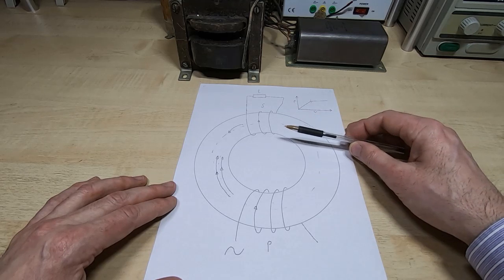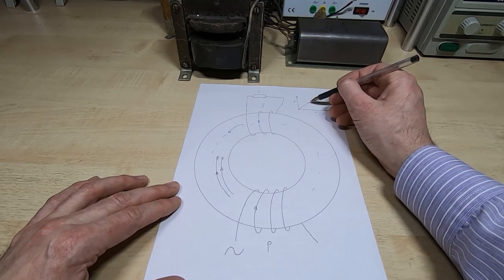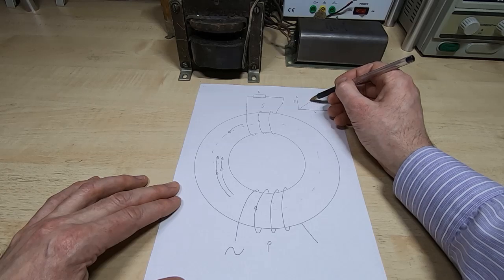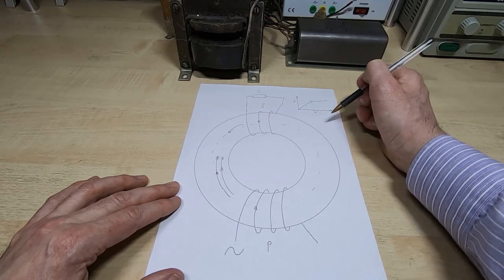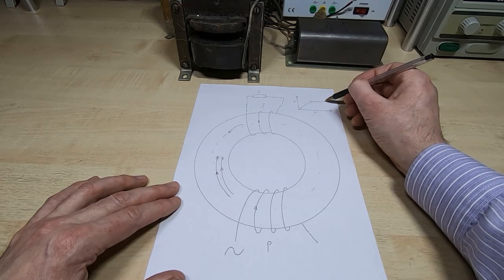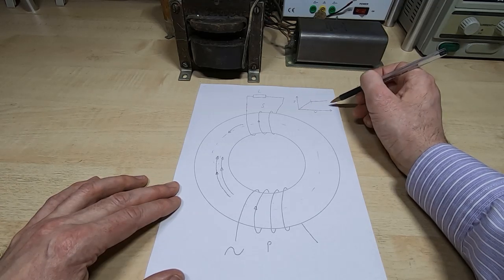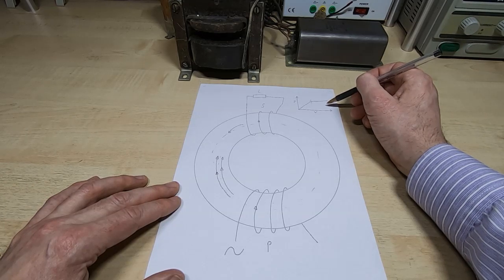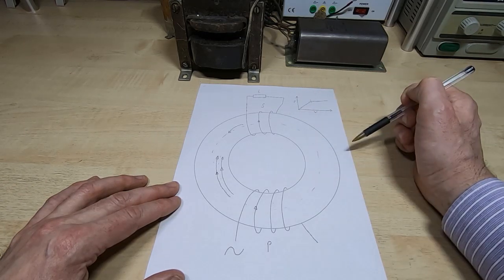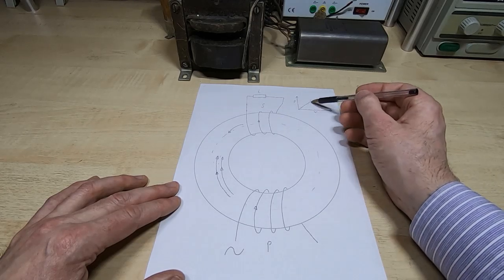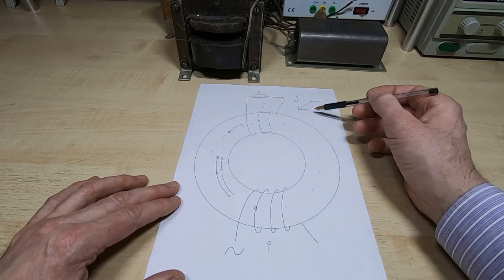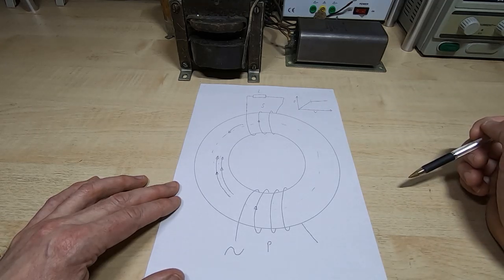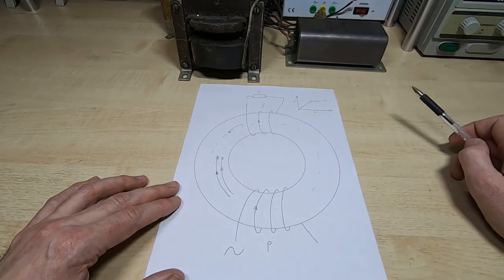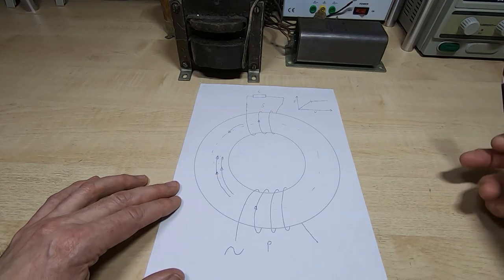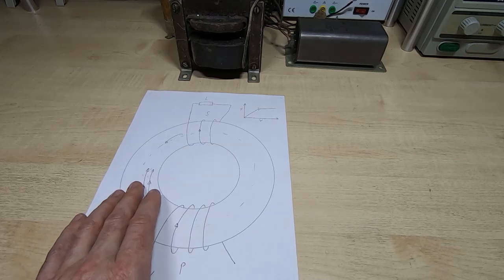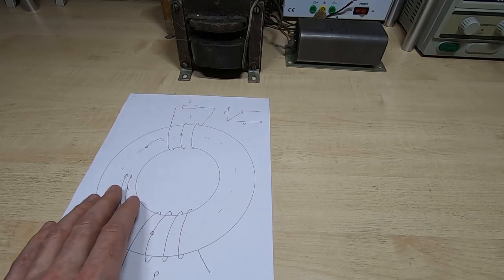The main difference with the ferroresonant transformer is that while the primary always stays, or should always stay, within this linear region, the secondary is designed to always run in this flatter saturated region. And that obviously begs the question, how can we have one winding on a common core in a linear part of the flux curve and the other winding in a saturated part? And that comes down to the way that the transformer is physically structured. So I'll get rid of this and we'll look at the general core design for a ferroresonant transformer.